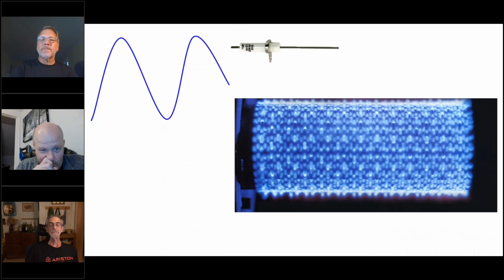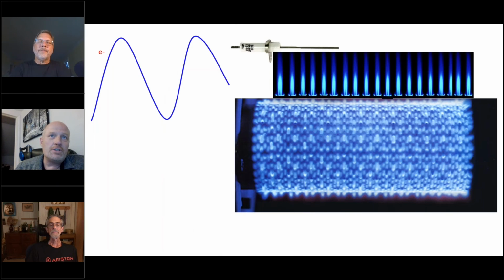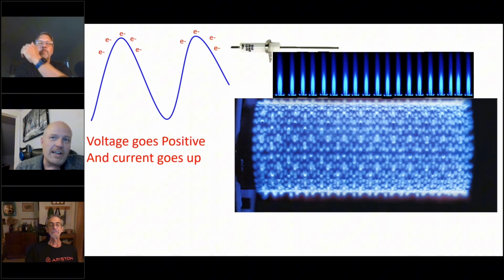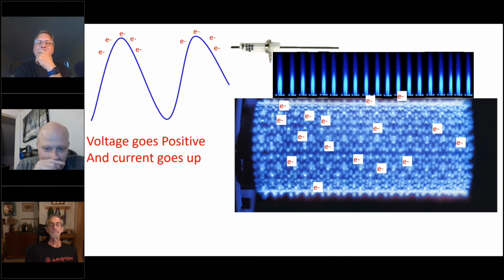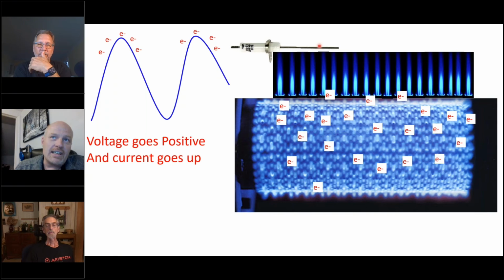Now, what happens when the voltage goes positive, or in the opposite direction, is that all of the electrons stick to the burner, because the chemical nature of the flame means that electricity cannot conduct backwards through it. It's fairly good at conducting electricity down, but it doesn't do such a good job of conducting it back up. And so what happens is your controller is monitoring this voltage.